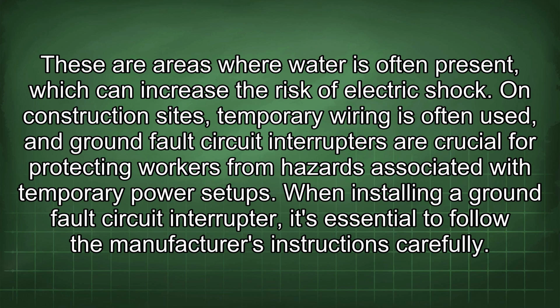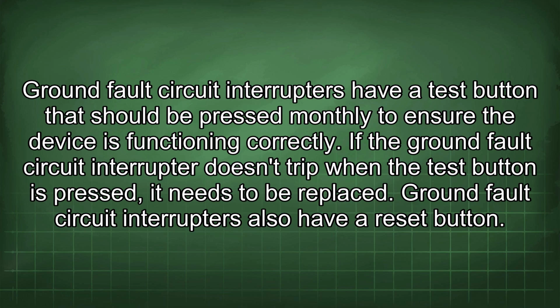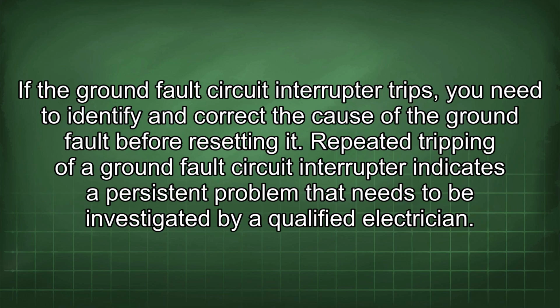When installing a ground fault circuit interrupter, it's essential to follow the manufacturer's instructions carefully. Ground fault circuit interrupters have a test button that should be pressed monthly to ensure the device is functioning correctly. If the ground fault circuit interrupter doesn't trip when the test button is pressed, it needs to be replaced. Ground fault circuit interrupters also have a reset button. If the ground fault circuit interrupter trips, you need to identify and correct the cause of the ground fault before resetting it. Repeated tripping of a ground fault circuit interrupter indicates a persistent problem that needs to be investigated by a qualified electrician.